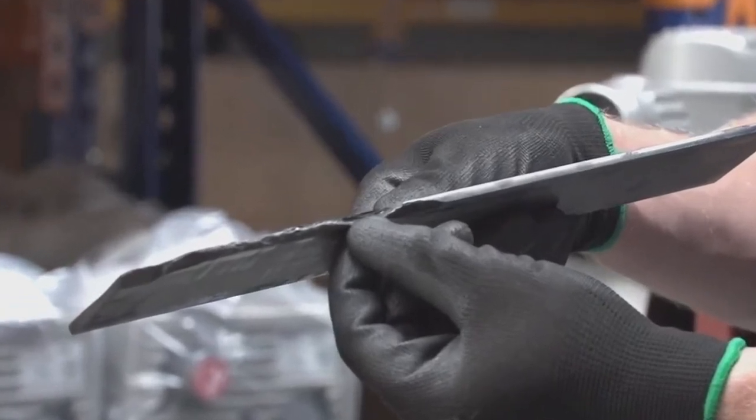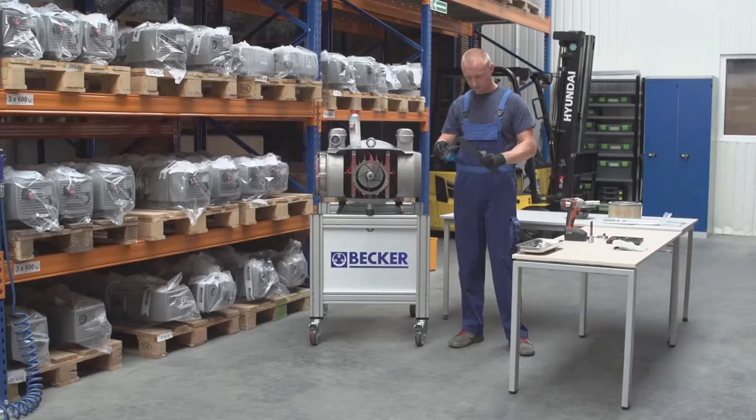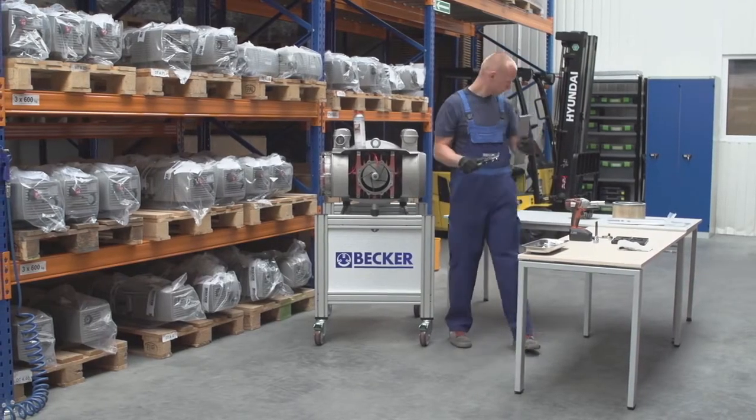Check each vane for chipped edges or cupping on the flat side of the vane. If the height of the vane is near or below the recommended minimum dimension, or has signs of excessive wear, the vane needs to be replaced.